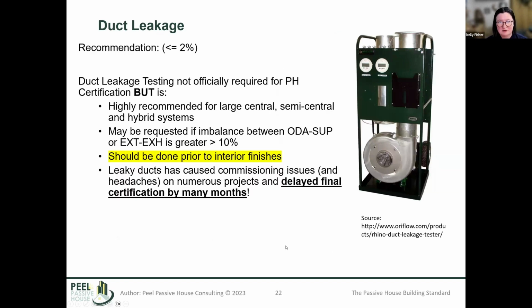For duct leakage, it is highly recommended that you do testing. For a lot of our consulting projects, we, at a minimum, request that duct leakage testing is performed. Our preference is to have AeroSeal done, but sometimes the budgets don't accommodate that. So duct leakage testing at a minimum, to better understand if there is leakage with the conventional means of sealing the ducts, because as Michael said, the contractors are always going to say that they've done it properly and perfectly, but that's usually not the case. There's always leakage that comes through, and that can really hurt us when we're looking to get everything appropriately balanced.